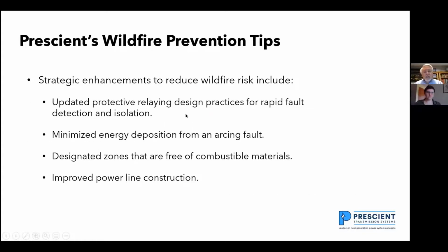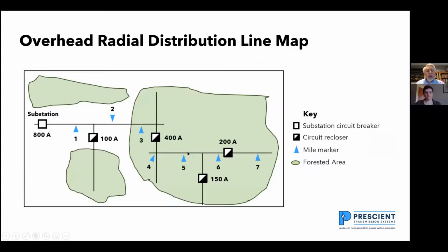Strategic enhancements that you can do to reduce wildfire risk. You have to update your protective relaying design practices for rapid fault detection and isolation. Right now, I'm setting my protective relaying up so that everything coordinates. If I go back a couple of slides, the way I set this up is if I have a fault at mile 5, the 400 amp recloser is supposed to actuate, and the 800 amp circuit breaker at the substation doesn't actuate to isolate a fault at mile 5. If I have a fault on this tap, I'm going to trip the 100 amp recloser, and I'm not going to trip the circuit breaker back at the substation.